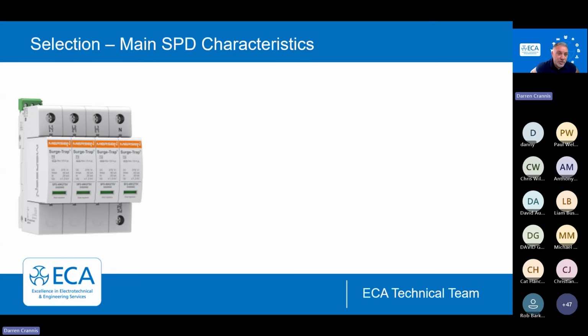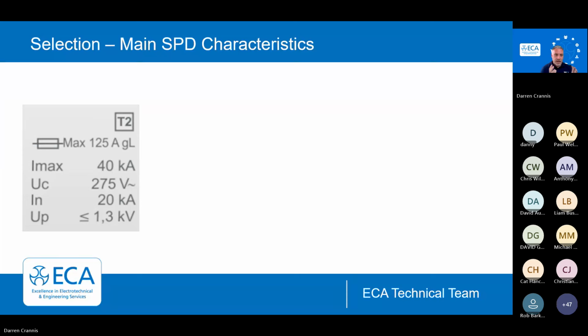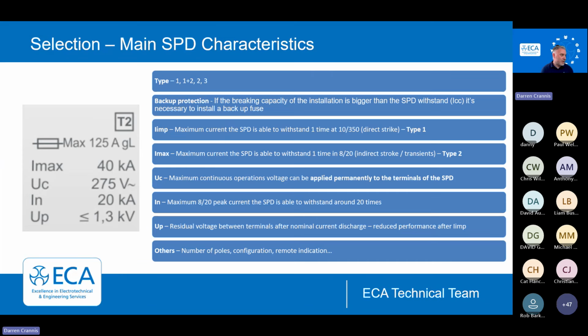We're used to picking up circuit breakers and fuses off the shelves, and we can read these normally really, really well. Can we do it out of SPDs? Now, hopefully, this will give you the confidence to check that you've got the right SPD. They have markings on them, just like MCBs. What does all this mean?